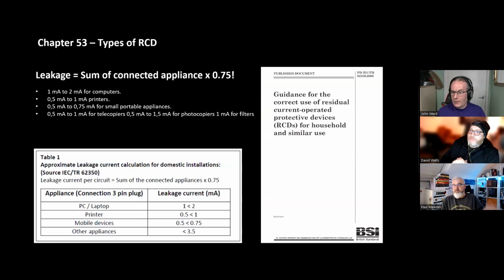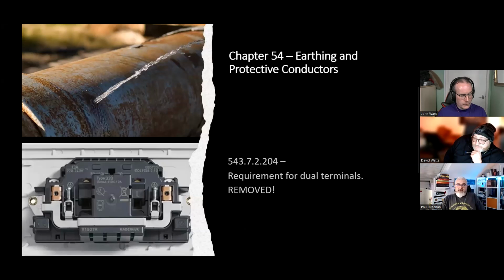Oh, one other thing, by the way, before we move on, apologies. If anybody wants to understand leakage of devices, that list is very small. That standard was written in 2006. If you go online and look for Schneider's RCD protection guide, it has an entire table where they've made that about 10 times bigger for cookers and all sorts, and it gives you the leakage there. So they've done a great piece of work. It's free. It's also got great information about RCDs. Obviously. Yep. It's free. Right, we'll move on.